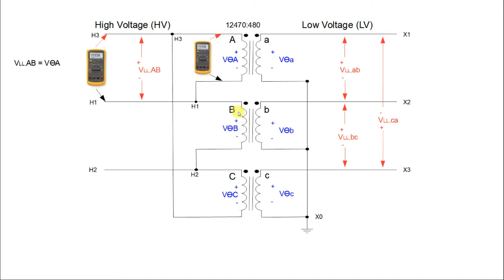Here is my V line to line, B to C. If you look, the polarized side of my B phase and the non-polarized side of B phase is the same point electrically as H2, so my line-to-line will equal my phase. The same is true for C: the polarized side of C is the same point as this line, and the non-polarized side of C is the same point as right here.